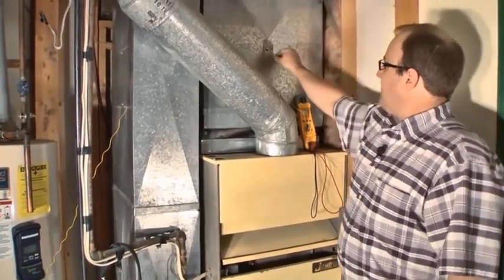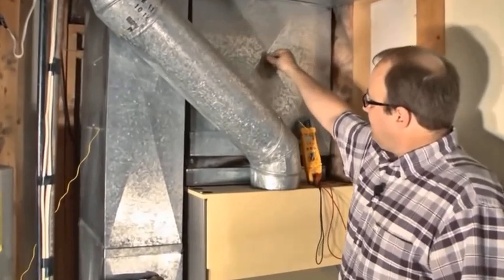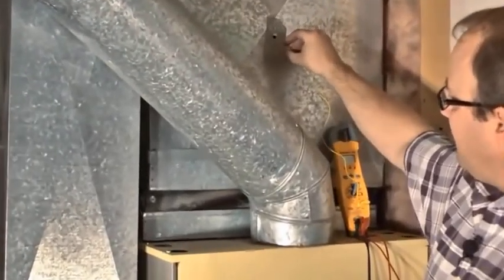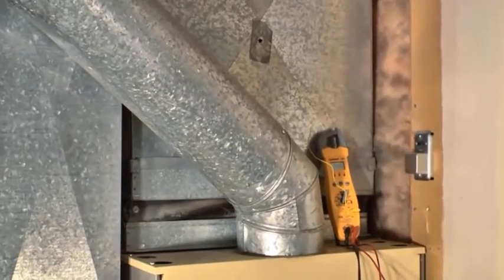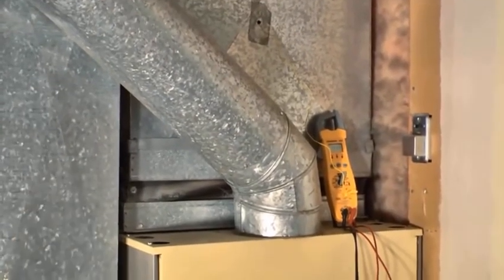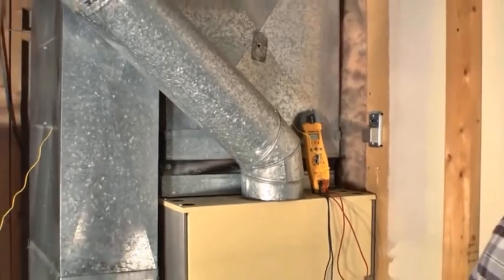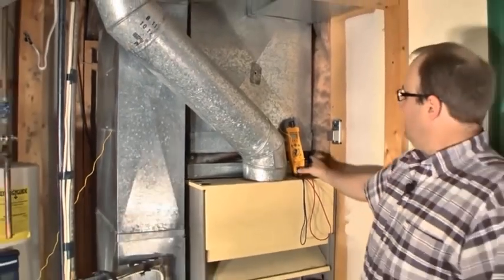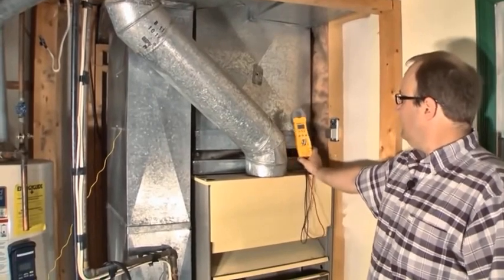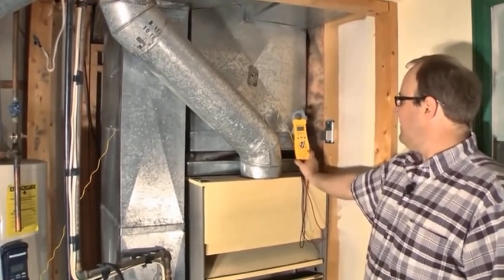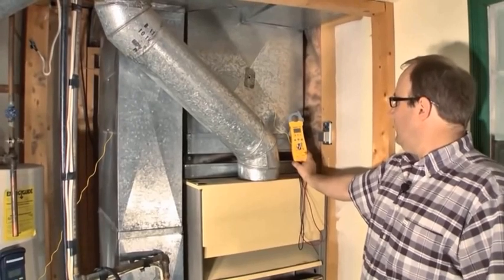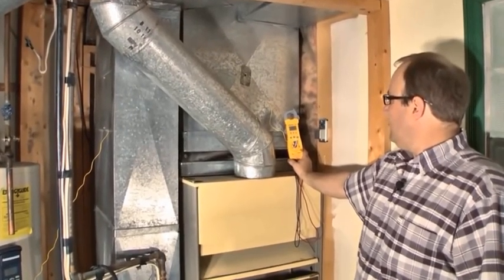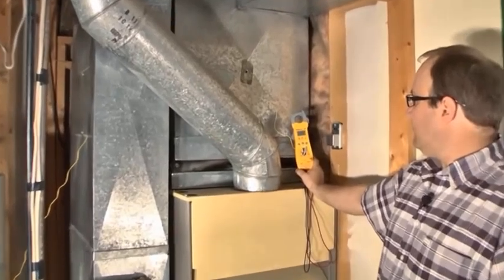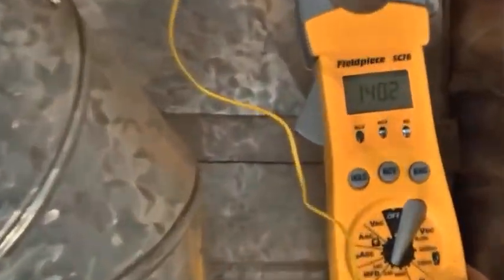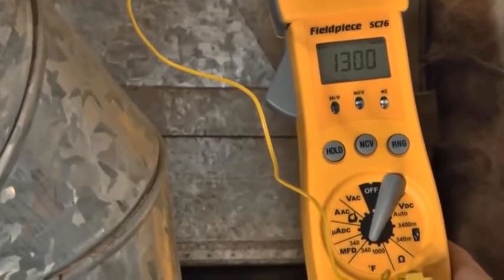So we're at 112 degrees right now. I like to use these probes because I can drop them down into the ductwork. It's kind of nice. I get a little more accurate temperatures. We like to see a fan on temperature from anywhere from 120 to 140. Try not to exceed 160. So the fan came on at about 140.